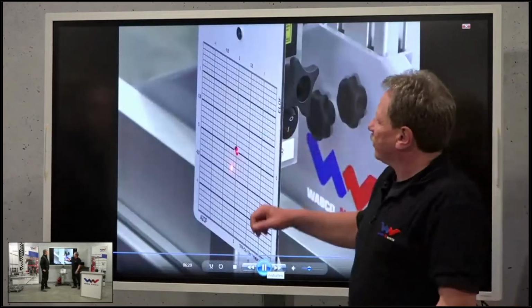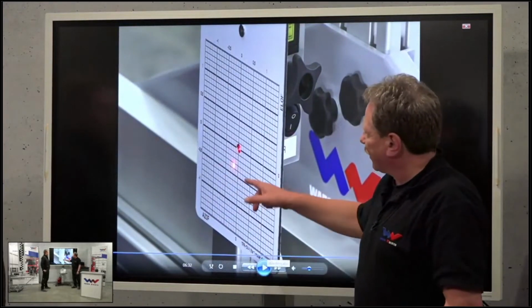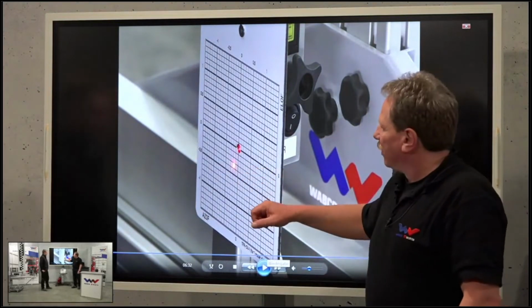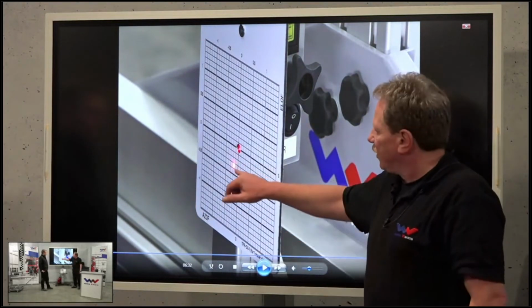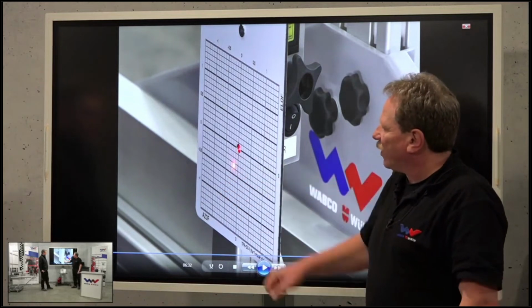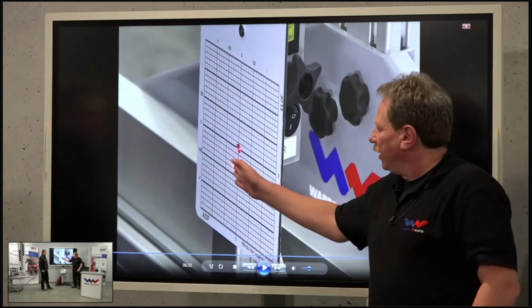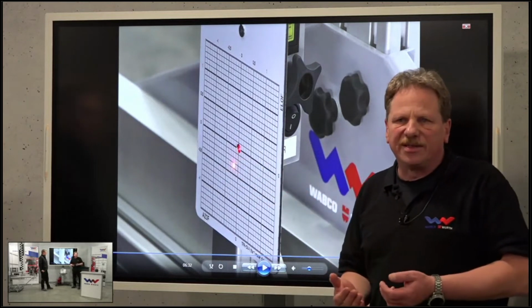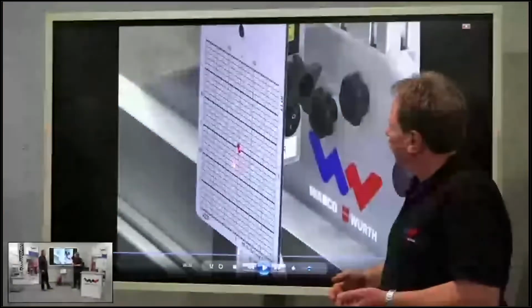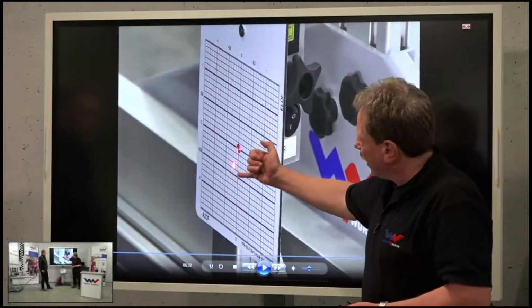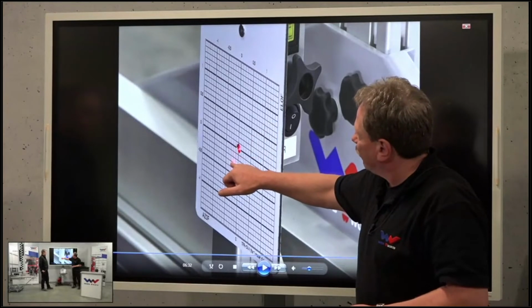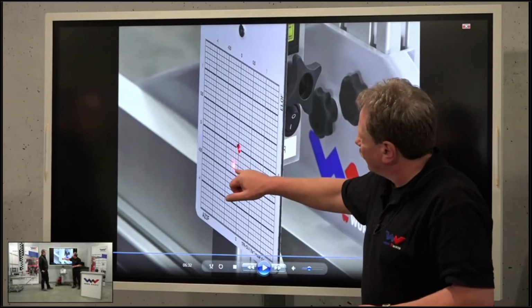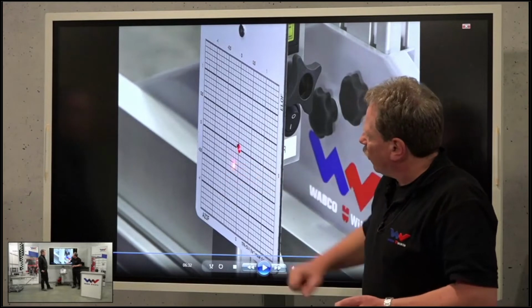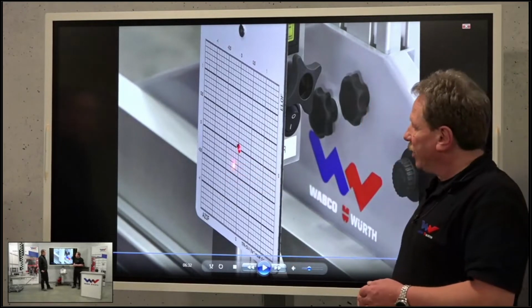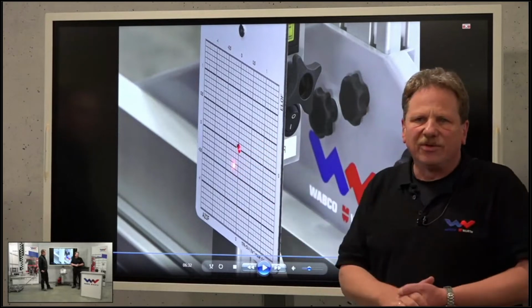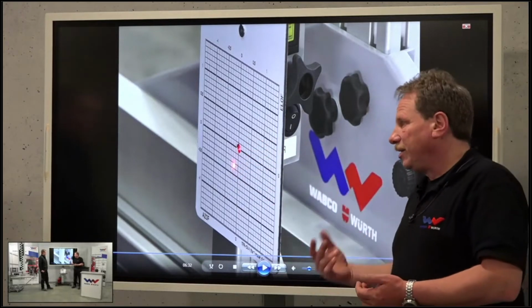So you see here also the dot, which is now reflected towards the target. So we have to adjust with the screws the point where it will be reflected. Depending on which direction you have to turn, it will move, and you put it to the two values 0, 0 and 0.2, where 0, 0 would be the line here, and minus 0.2 would be to the left, to the second line. So one level is already near to be good, and the other one has to be screwed up. So then we have set up the second step in the radar calibration.